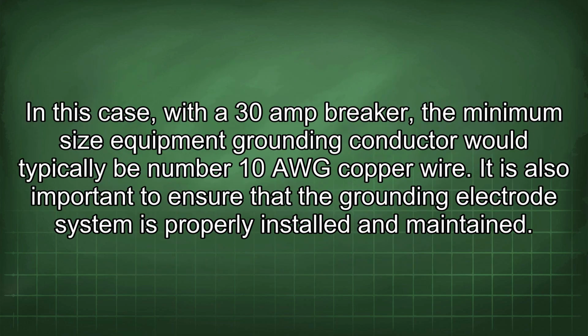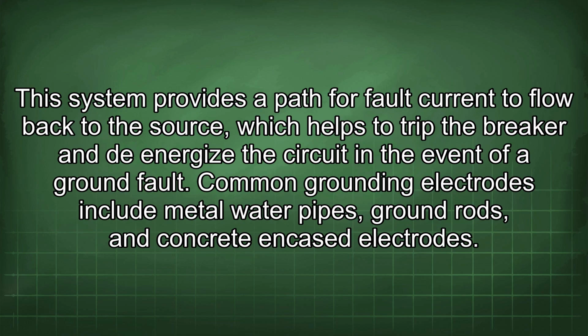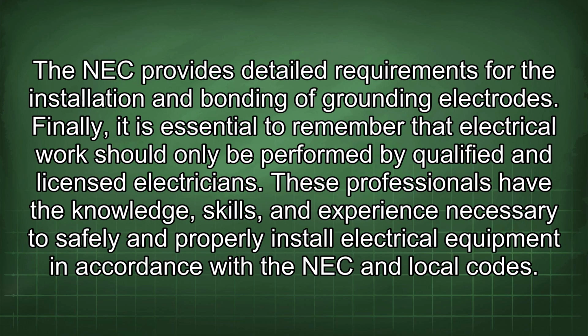In this case, with a 30 amp breaker, the minimum size equipment grounding conductor would typically be number 10 AWG copper wire. It is also important to ensure that the grounding electrode system is properly installed and maintained. This system provides a path for fault current to flow back to the source, which helps to trip the breaker and de-energize the circuit in the event of a ground fault. Common grounding electrodes include metal water pipes, ground rods, and concrete encased electrodes. The NEC provides detailed requirements for the installation and bonding of grounding electrodes.